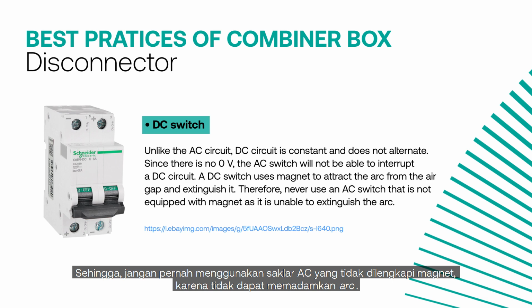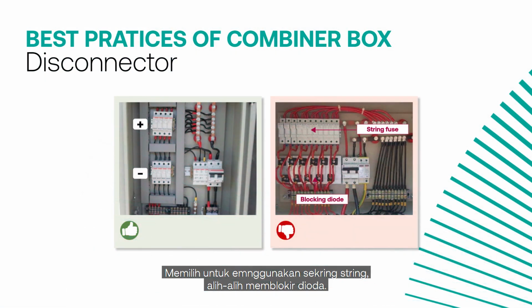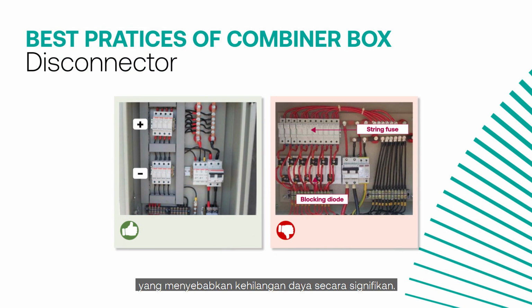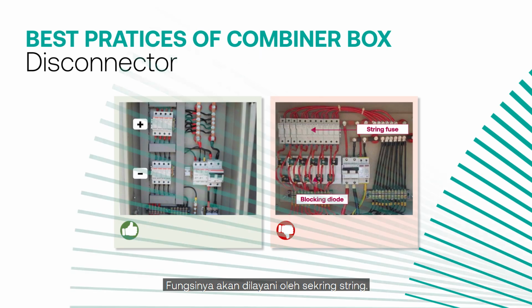Therefore, never use an AC switch that is not equipped with a magnet, as it is unable to extinguish the arc. Option to use a string fuse instead of blocking diodes. Blocking diodes cause an additional voltage drop of about 0.5 to 1 volt that leads to significant power losses. The function is better served by a string fuse.